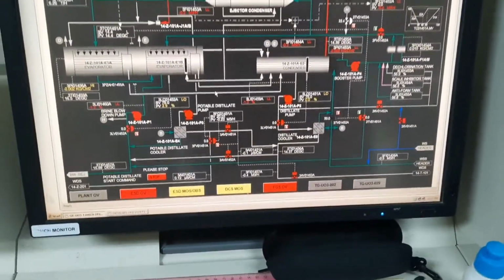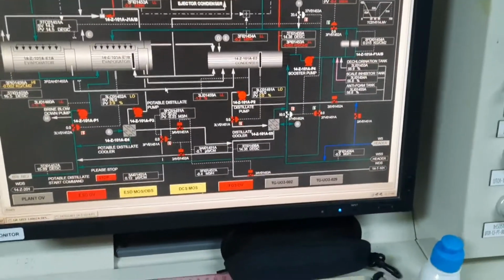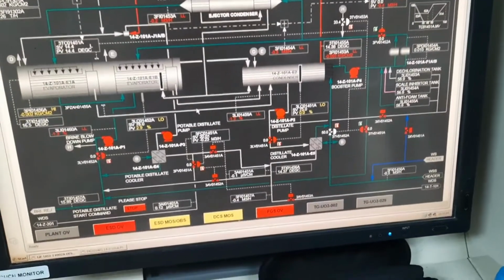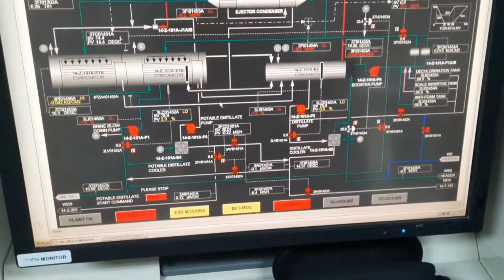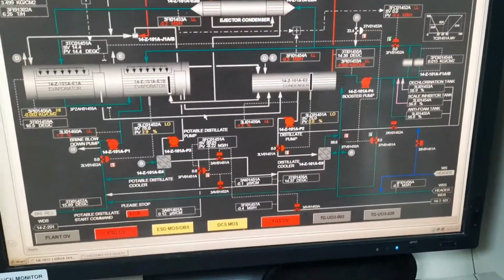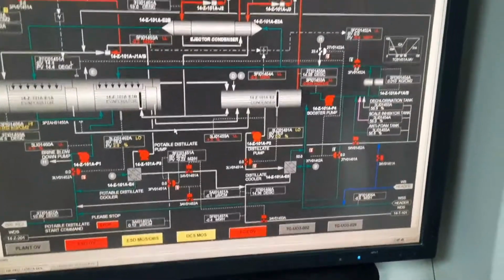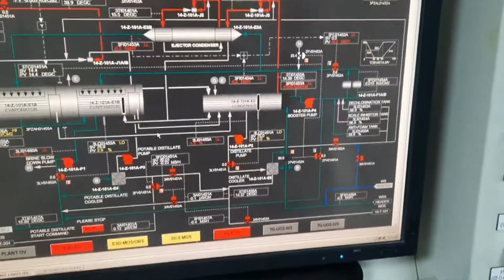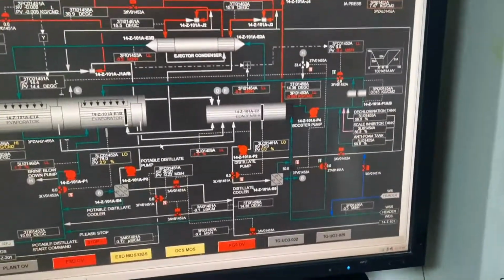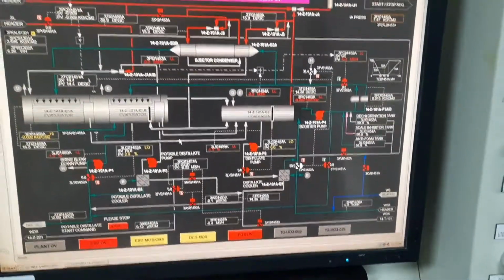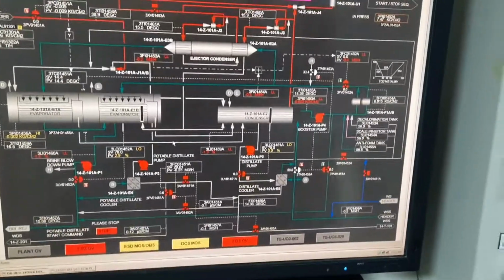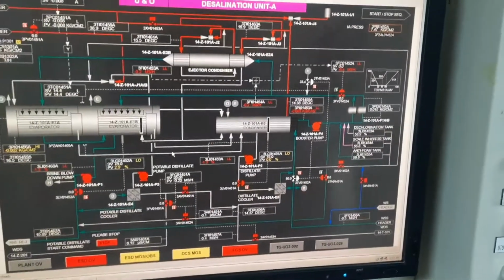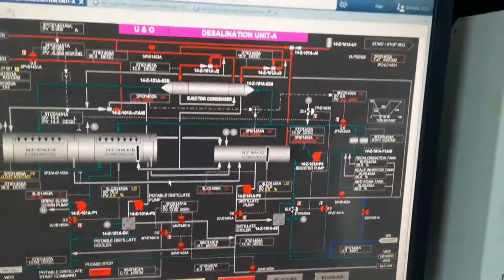When all the water is neutralized and discharged to the outfall, after that we need to remove the CO2 and hydrogen. To remove the carbon dioxide and hydrogen, we will break the vacuum and open all the drain valves. Again we fill up water, again create vacuum, again break the vacuum. If you do vacuum create and vacuum break two times, the gases will be released by the drain valve. After that, at least 4 or 8 hours of water circulation is needed.